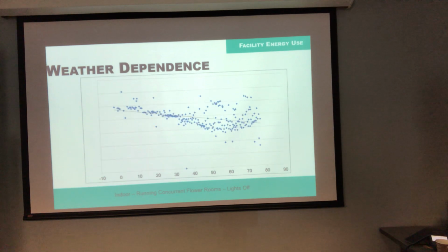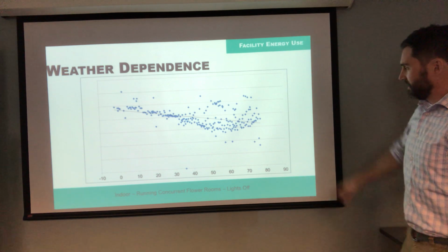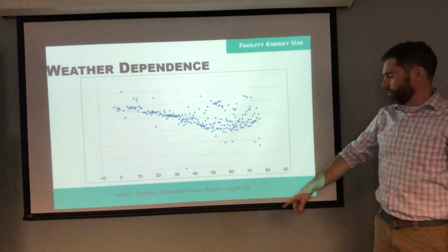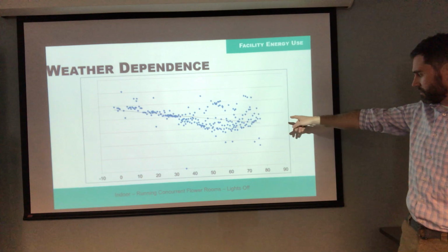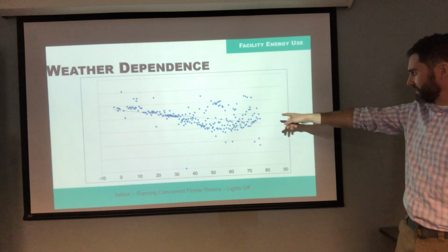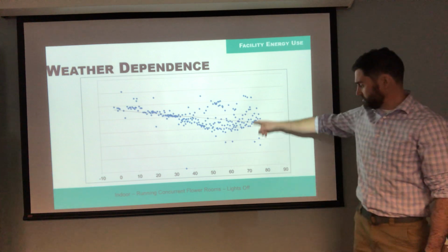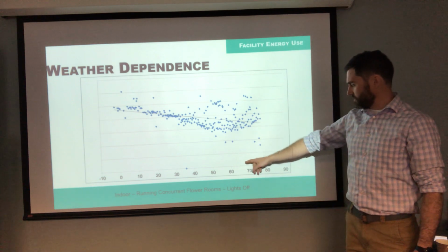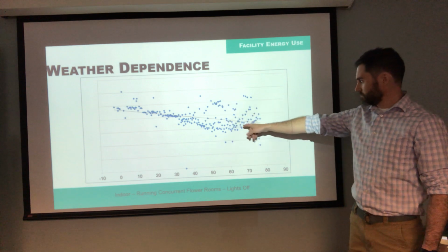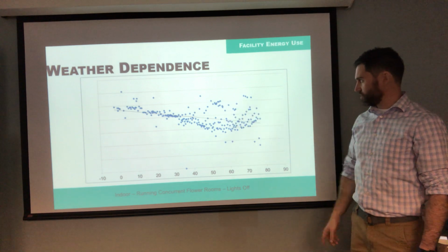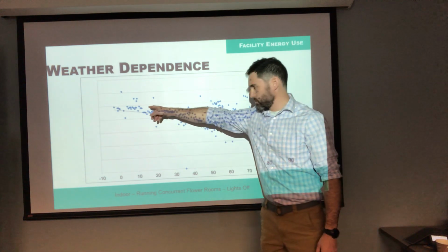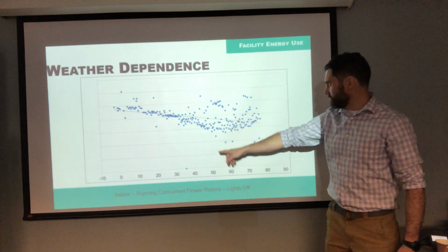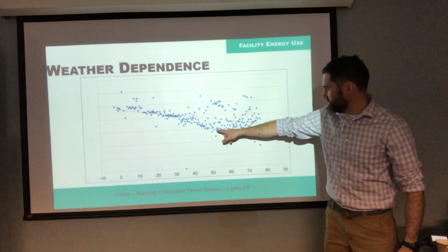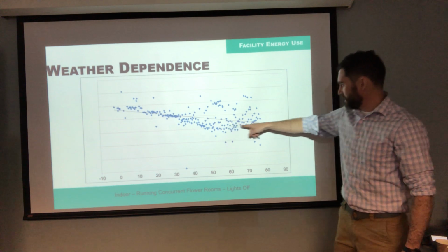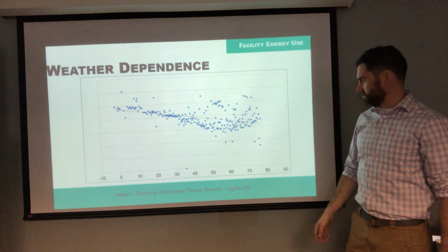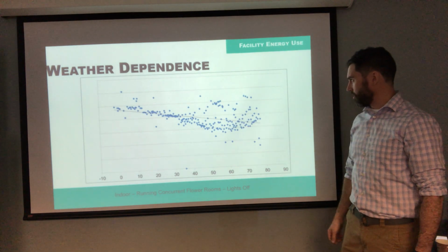What about the same facility when the lights are off? Again there's a lot of scatter, but clearly something different is happening. We see a downward sloping trend, so there's some weather dependence here. Depending on the outdoor temperature, my average kW changes, sloping downwards. This facility is using more energy in the cold, less energy somewhere around here, which might be the balance point, and beyond that their AC usage ramps back up even when the lights are off.